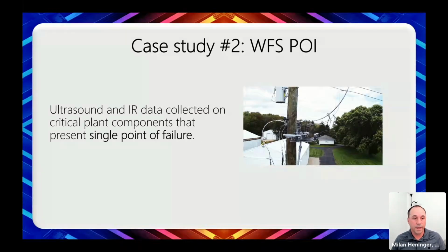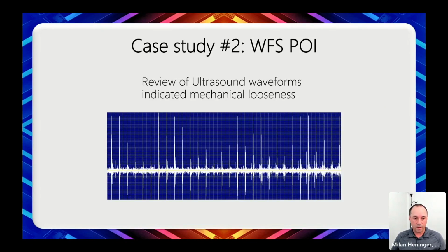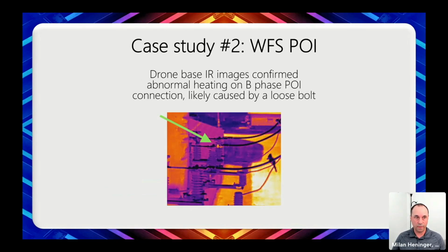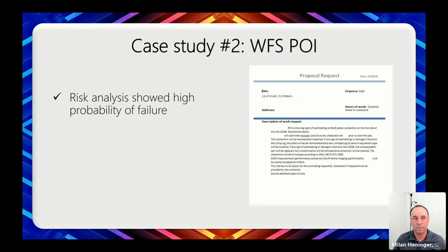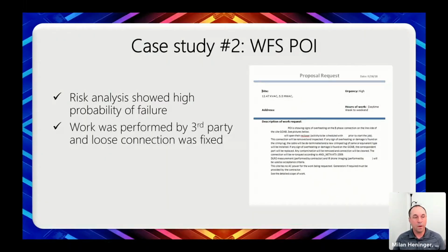Here's another one at the point of interconnection. There's a drone photo. Again, with ultrasound and IR, we saw that there was an issue at the single point of failure, right? On our POI, we don't have redundant POIs. Our ultrasound waveforms indicated mechanical looseness, and the drone showed that there was some heating occurring right there. Again, likely caused by a loose bolt. Due to the heating, we understood that this is presenting a high risk of failure. We had to get a third party in, but they were able to go in there. They identified the loose connection. They cleaned everything up, put it back together, and solved that problem as well.